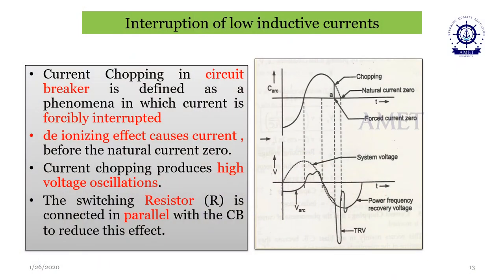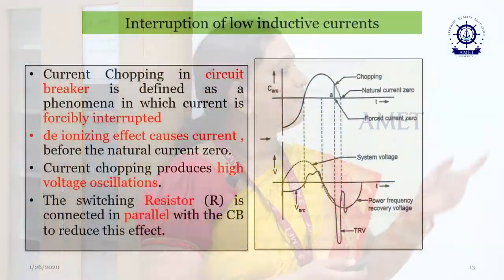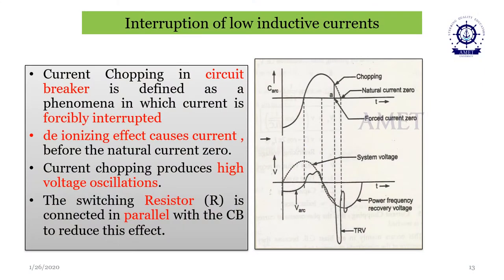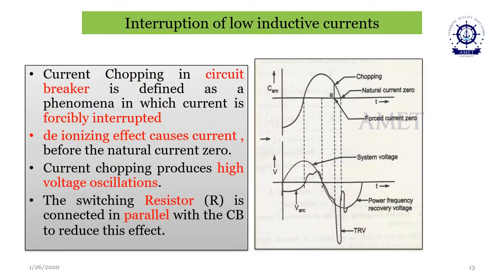Let us see what happens in the system by interrupting low inductive currents. So we know very well, see the picture, x-axis and y-axis, we have a two-part diagram. The upper part explains the circuit breaker current, say the arcing current at the circuit breaker. And we know very well, a circuit breaker makes or breaks the circuit under abnormal situations. So we know very well, current chopping. Current chopping is a phenomenon in which we forcibly interrupt the currents, that is, the low inductive currents.